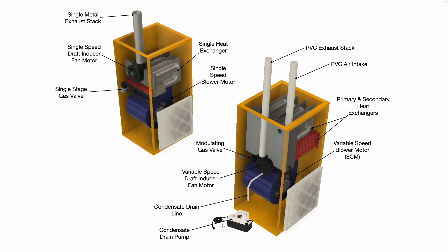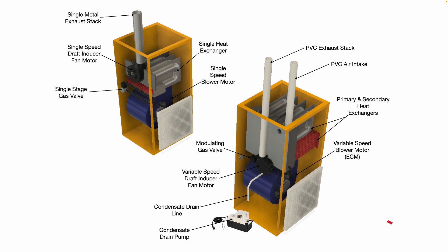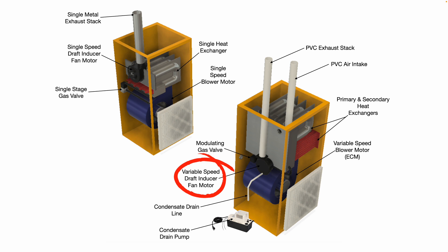As I mentioned, you can see we have a primary and a secondary heat exchanger — that's one of the big noticeable differences. We also have a variable speed blower motor like an ECM motor, a modulating gas valve, a variable speed draft inducer fan motor, and the addition of a condensate drain line.